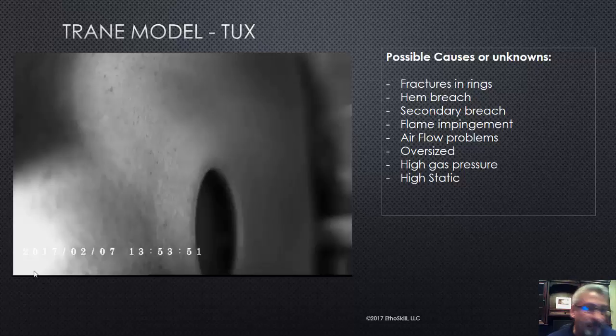So what happened? Why did this happen? I'll be honest, I don't know. But I'm going to tell you what I think, give you my opinion why I think it could have happened. First off, any draft-induced or vent-motored furnace, 80%er or high efficient, the heat exchanger is under negative pressure. So if you have a breach in that hem, in the rings, in a gasket on a coupler box or collector box, a secondary breach, anything where it's drawing air in where it's not supposed to, that means that it's not drawing air all the way through that firebox and past those burners, which then could cause other areas of that heat exchanger to overheat.